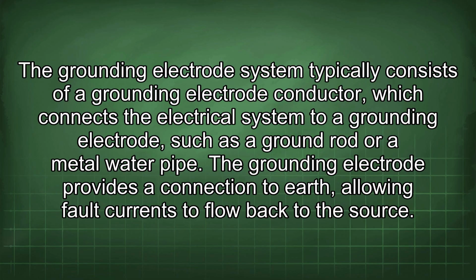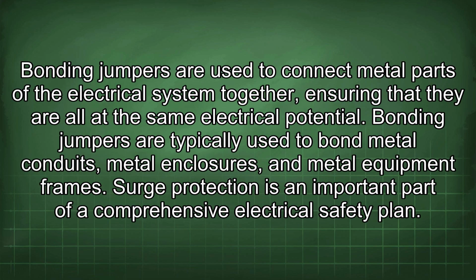The grounding electrode system typically consists of a grounding electrode conductor, which connects the electrical system to a grounding electrode, such as a ground rod or a metal water pipe. The grounding electrode provides a connection to earth, allowing fault currents to flow back to the source. Bonding jumpers are used to connect metal parts of the electrical system together, ensuring that they are all at the same electrical potential. Bonding jumpers are typically used to bond metal conduits, metal enclosures, and metal equipment frames.